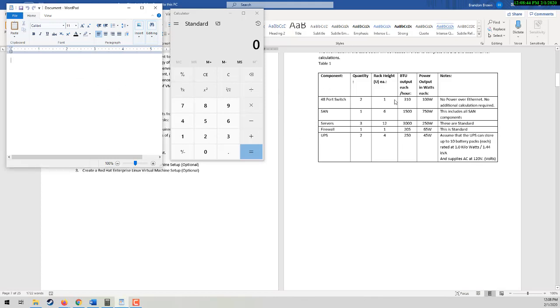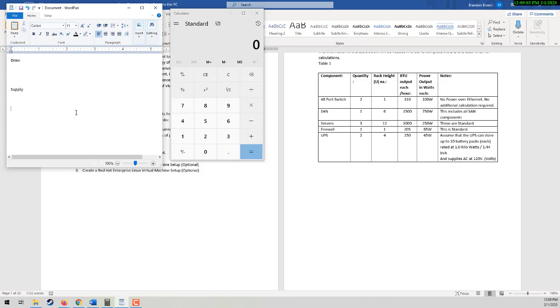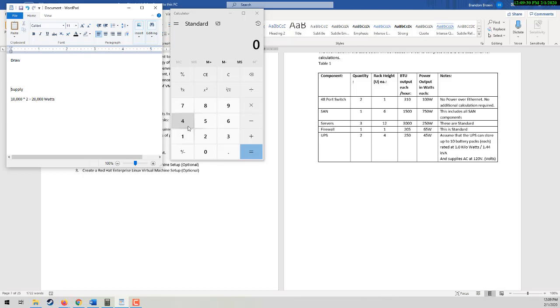So we need to calculate up our draw and our supply. Let's work with supply first. Supply is pretty easy. Assume that the UPS can store up to 10 battery packs each at 1 kilowatt. So that's 1 kilowatt times 10. That's 10 kilowatts or 10,000 watts. And then we have two of them. So that is going to actually be 20,000 watts. That's our supply, 20,000 watts.